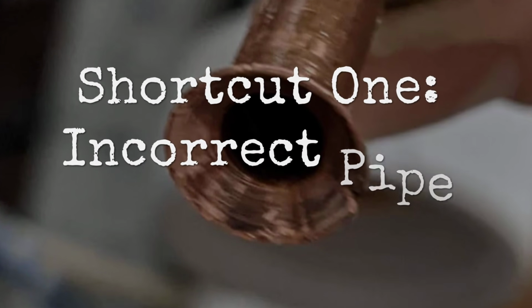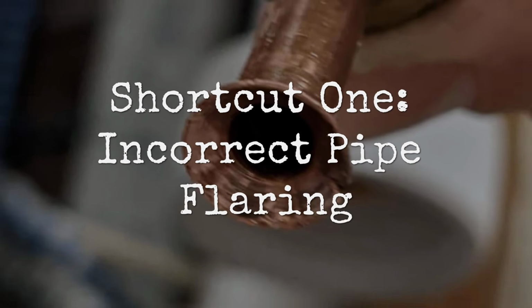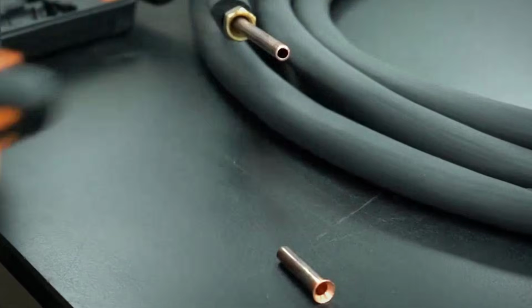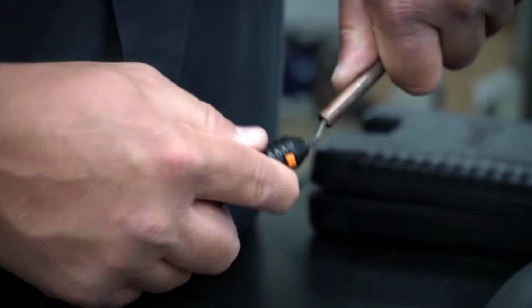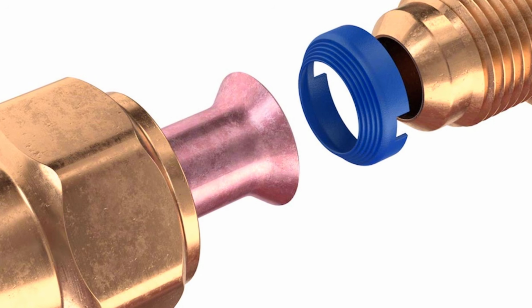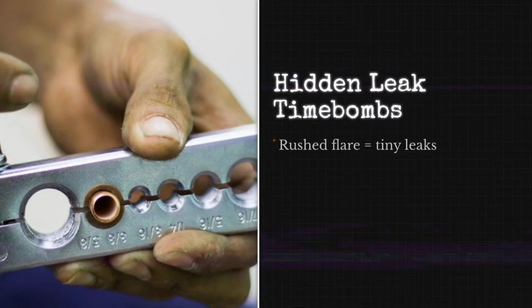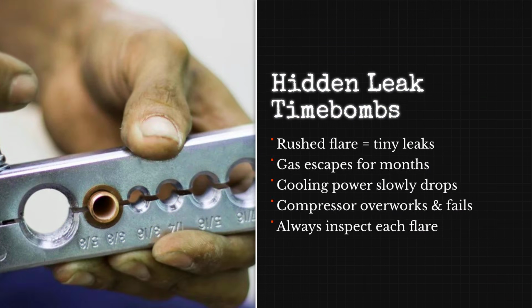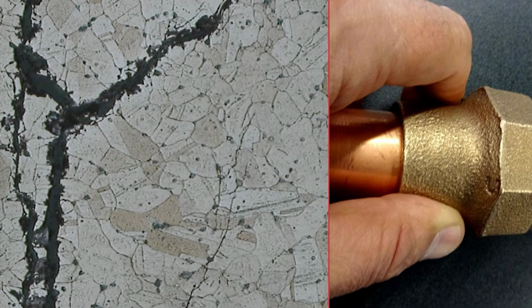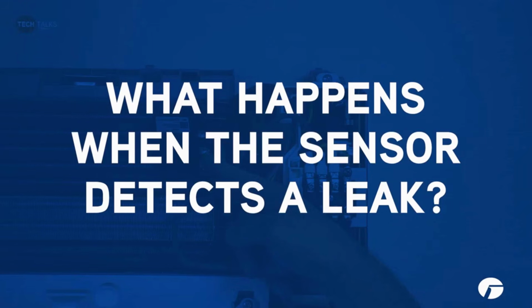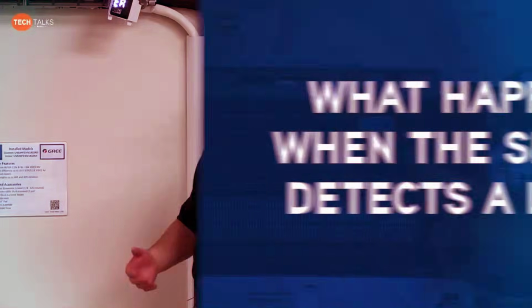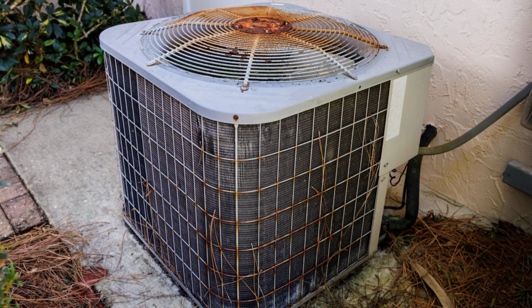Shortcut 1. Incorrect pipe flaring. The copper pipe connecting the indoor and outdoor unit has to be flared at both ends to create a seal against the refrigerant fittings. Correct flaring requires a calibrated flaring tool, correct technique, and a visual inspection of the finished flare before connection. Rushed flaring produces micro cracks in the flare face that are invisible at installation and produce a slow refrigerant leak over the following 18 to 36 months.